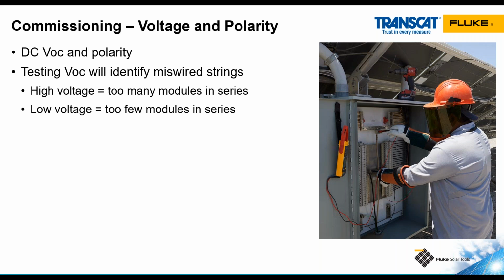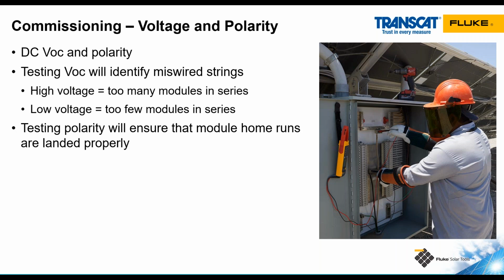Now at the commissioning stage, some very simple but critical tests are testing DC open circuit voltage and polarity. We're testing open circuit voltage to ensure that we connected the proper number of modules in series. First we need to calculate what our expected voltage is. Then if we see voltage that is too high, we know we connected too many modules in the circuit. If the voltage is too low, we connected too few, and those issues are typically paired together where one string is too high and one string is too low.